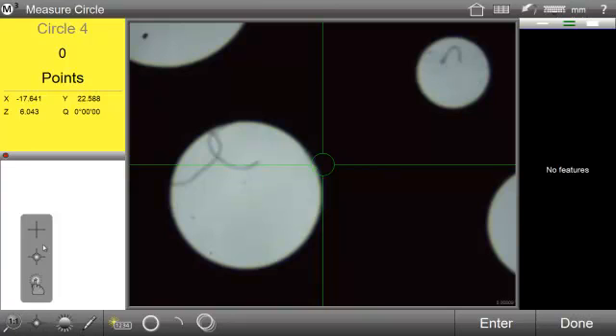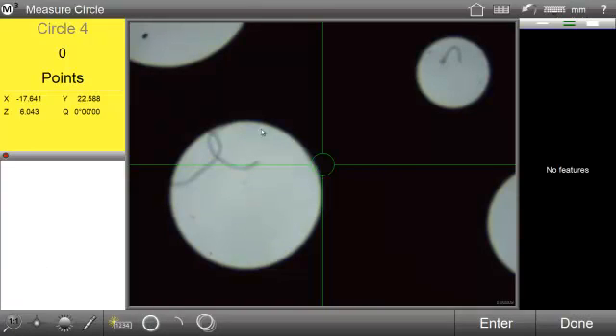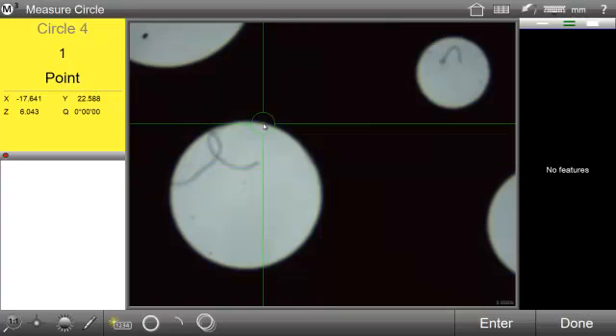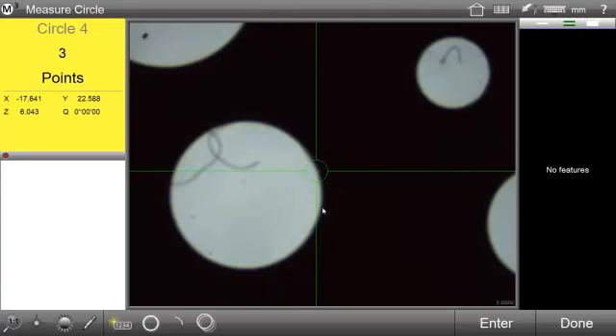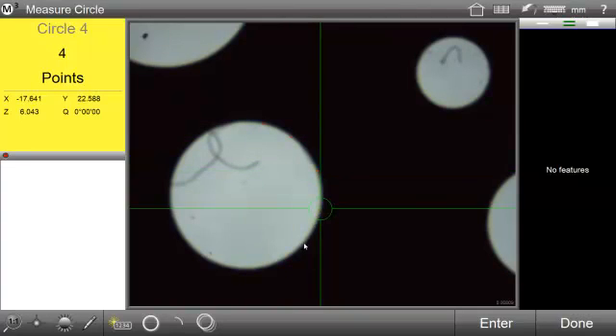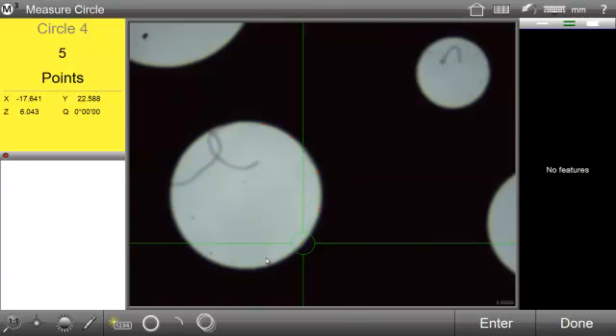Next, select the measure circle button from the bottom toolbar and then probe at least a minimum of three points of a circle feature being measured by clicking or pressing on the feature's edge.